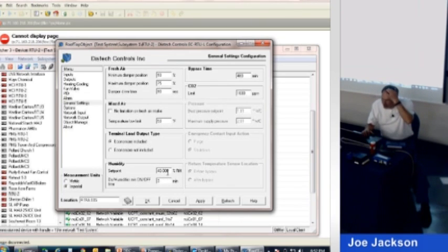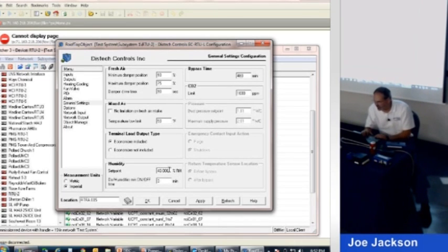Here's the humidifier information. Right now, when we drop below 40% relative humidity, we're going to turn on the humidifier, and it's going to stay on or off for a minimum of 3 minutes. We put a CO2 sensor in there, so when we go over 1,000 parts per million, if that happens, we're going to start to open the outside air damper a little more than the 10% that we set.